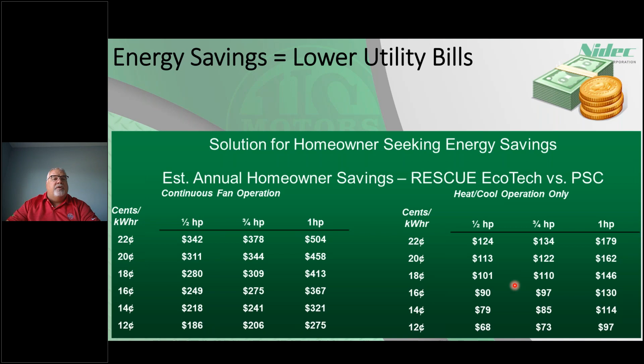Here's another look at that energy savings. Here's a 90K BTU unit, and the PSC was drawing about 580 watts, and then on continuous fan, because in a furnace the continuous fan on a PSC is usually the heat speed, it ran at a little below 500 watts. When we put the EcoTech into the same unit, it was about 410, then it dropped down to 90 watts like I mentioned. That energy savings of 394 watts is a huge savings. Over here is a larger unit with even more savings, 576 watts. So you get the idea.